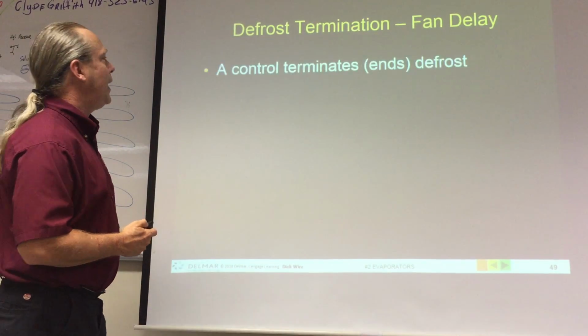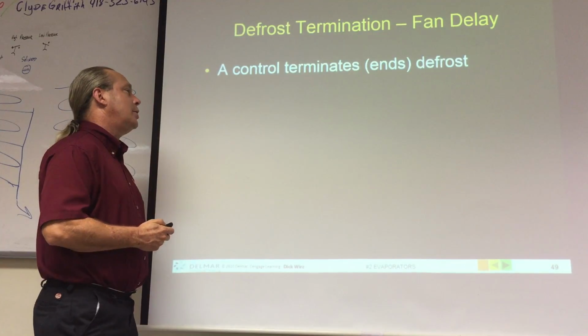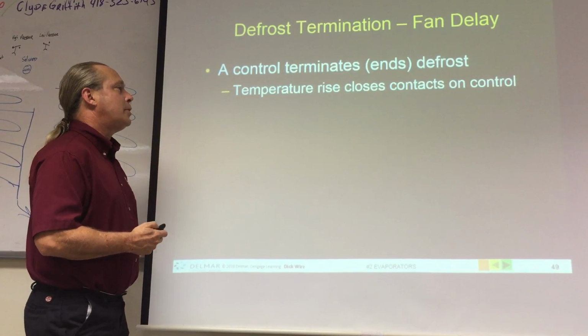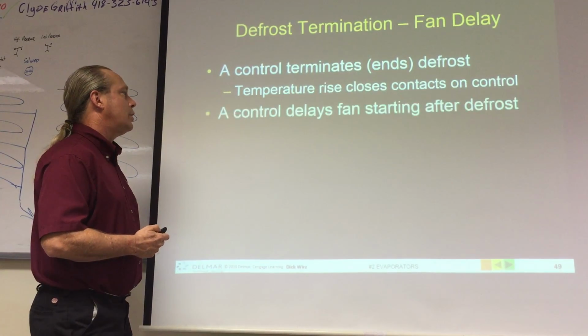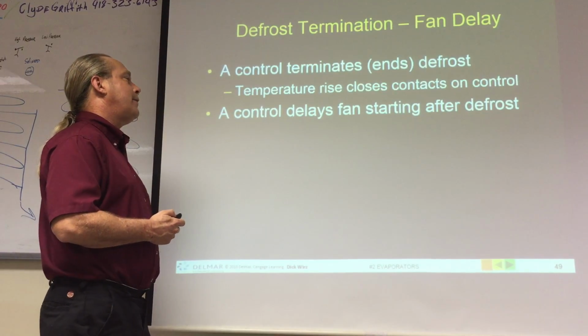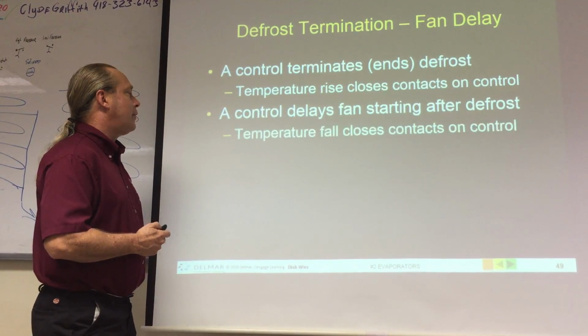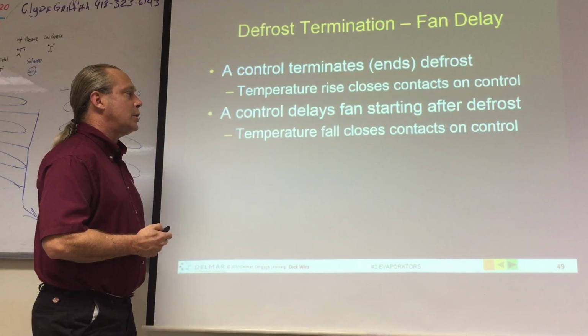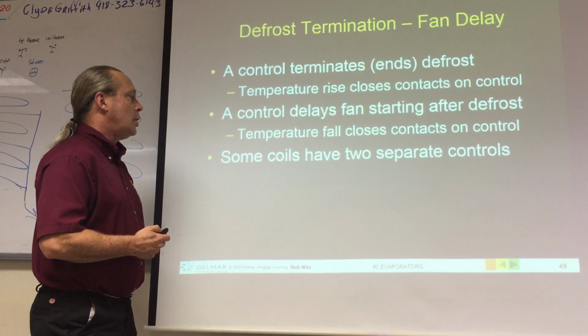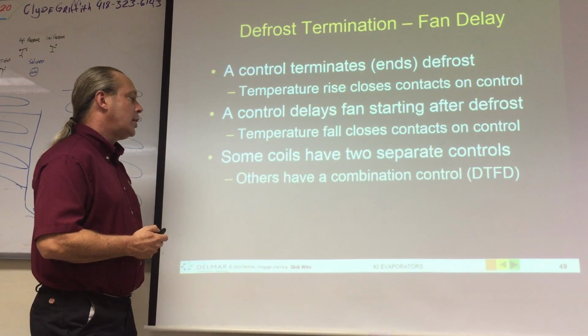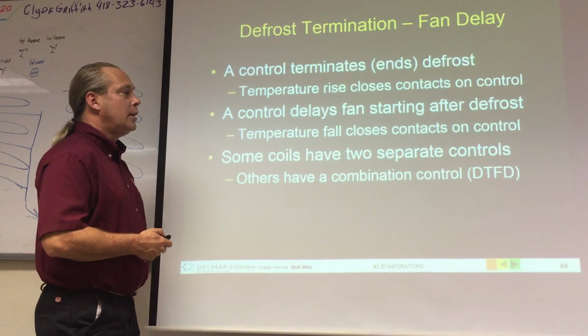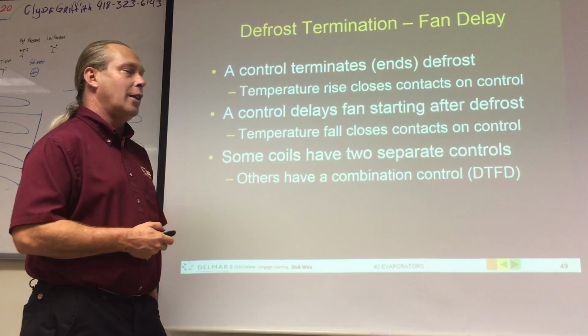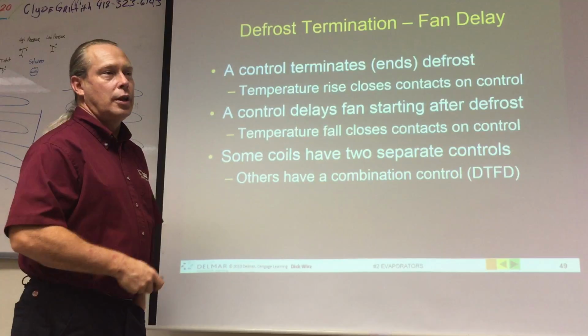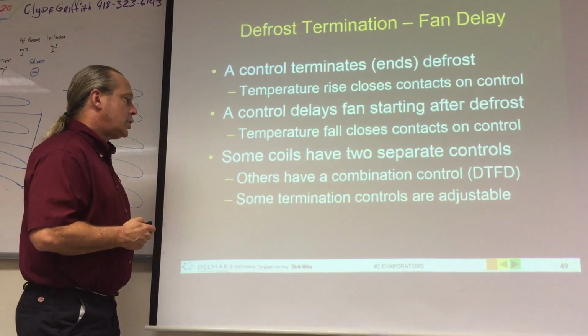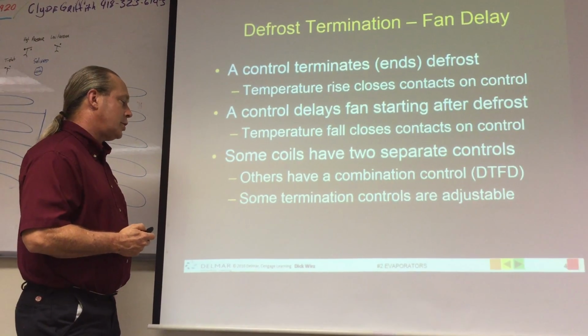Defrost termination and fan delay. The control terminates or ends the defrost. The temperature rise closes the contacts on the control. A control delays fan starting after defrost. The temperature fall closes contacts on the control. Some coils have 2 separate controls. Others have a combination defrost termination, fan delay, single little unit on there. Some termination controls are adjustable.